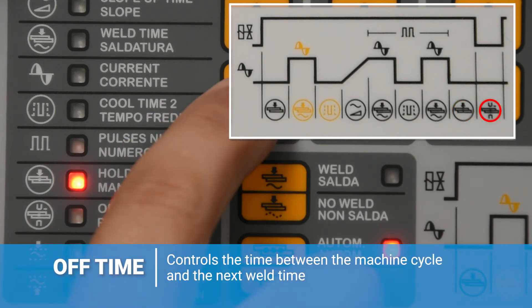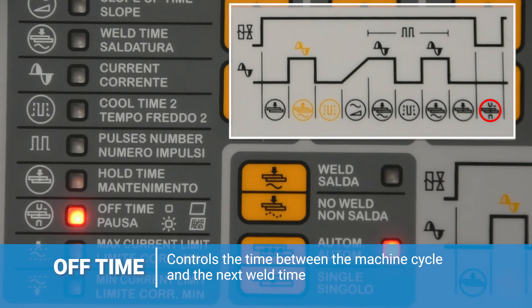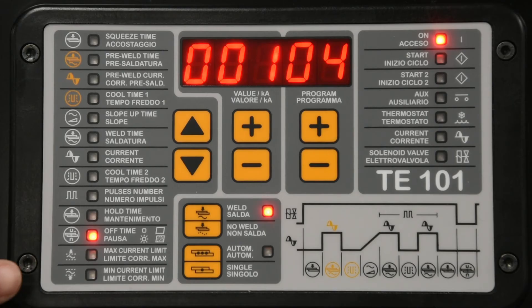Next is the off time. This is used in automated welding and controls the time between the machine cycle and the next weld time. This can be set between 1 and 99 cycles. The final two parameters, the maximum current limit and the minimum current limit, can be set between 0 and 56 kiloamps and will generate an error if the welder sees a current value exceeding these thresholds. When set to 0, these functions are off.